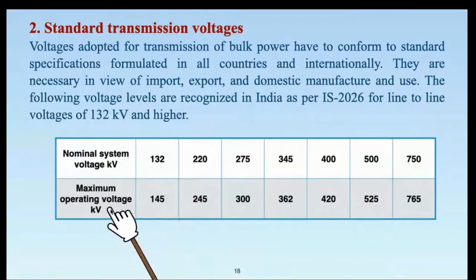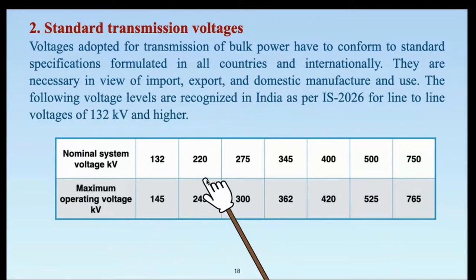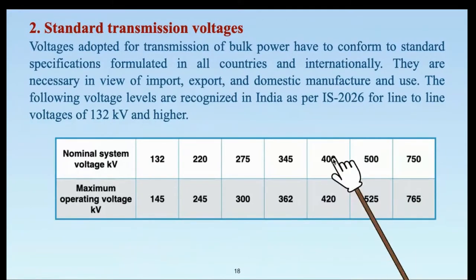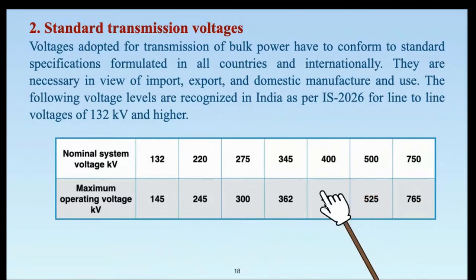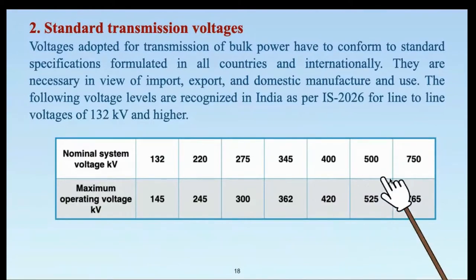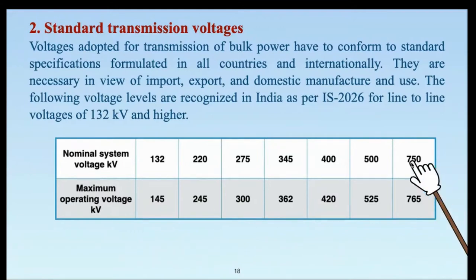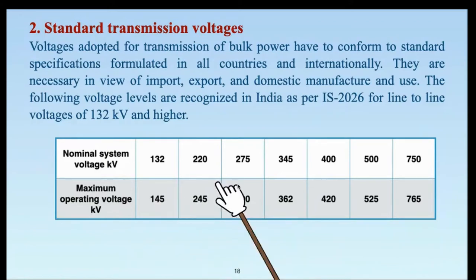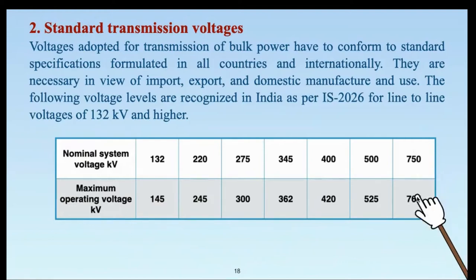At 132 kV, the difference between maximum operating voltage and nominal system voltage is nearly 10 percent. As we move higher up the scale to 400 kV, the difference between 400 kV and 420 kV is only five percent. At still higher voltages — 750 kV and 765 kV — this difference may be around two percent. So as we move from 132 kV to higher voltages, the margin between nominal system voltage and maximum operating voltage becomes very very small.